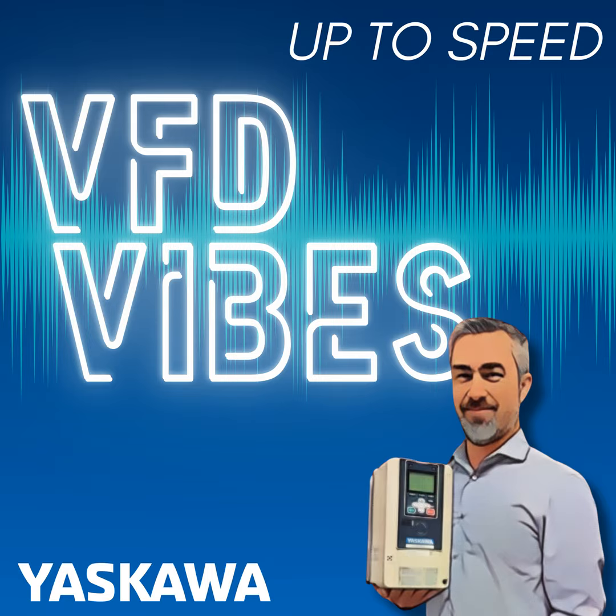So it could affect longevity of the drive. Could it cause other issues, nuisance trips or faults or things like that? Yes, you can get some nuisance tripping on a lot of other equipment because the system is ungrounded. So it may not be the drive actually nuisance tripping, but because of the reflected power that it's distorting onto the system, other devices might trip or give you errant readings if it's a high sensitivity level sensor or a flow sensor, things like that.